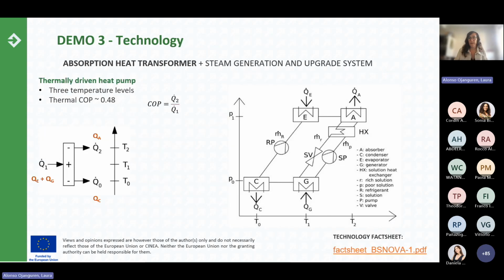Okay, here again, a representation of the 3 different temperature levels of the absorption heat transformer, because this is quite a different technology if you compare it with the compression heat pumps. So we introduce the waste heat in the evaporator and in the generator. In this case, we are introducing the waste heat in series in these elements. We upgrade heat in the absorber, and we reject heat at a lower temperature in the condenser.